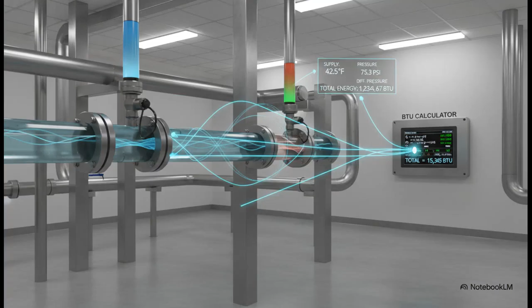So how does it do all that? Well, it's packed with a whole suite of high-tech sensors. It's got ultrasonic flow meters to track the exact volume of water, super precise temperature sensors to measure the change from supply to return, and pressure transmitters that monitor the system's force. All of that data gets fed into a central BTU calculator that crunches the numbers in real time for billing.